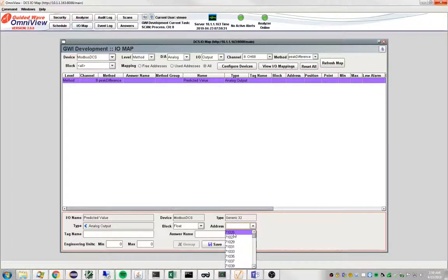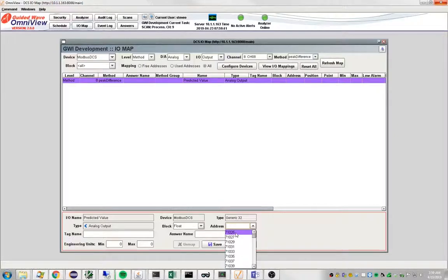Next, we assign an address. Now, we have kind of an unconventional numbering scheme with Modbus here. This 71,000 series address, it really gets mapped to a proper Modbus address. So I'm going to select this address, 71025.